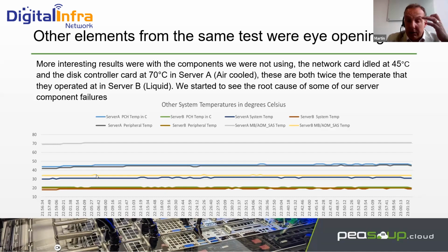Part of that is the architecture of the servers - these came with 6 fans but could take 8, and the controller was on the left, so it could have had an additional fan. More things could have been done, but it's not a consideration we'd normally have. We did get a bit of a shock noticing it was running at 70 degrees just on tick over.